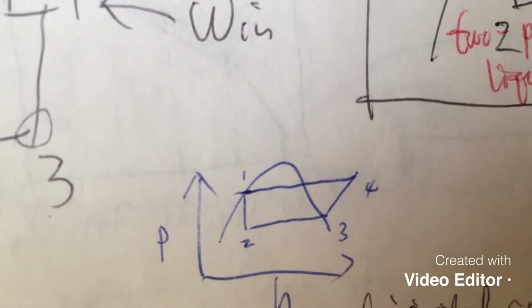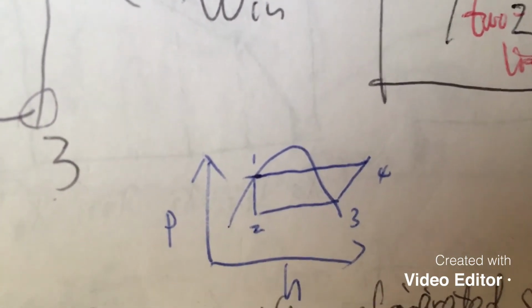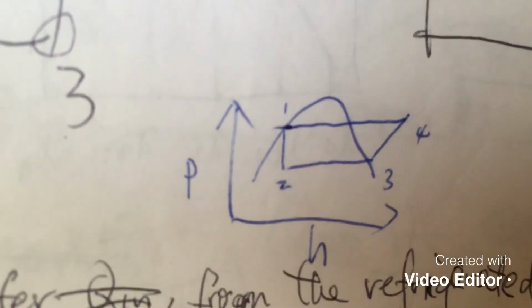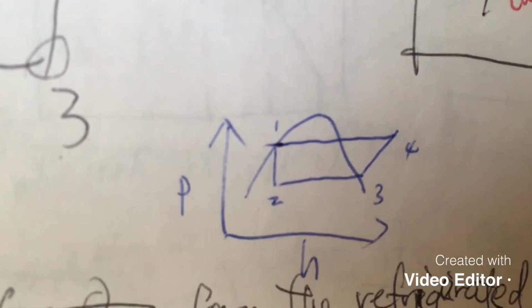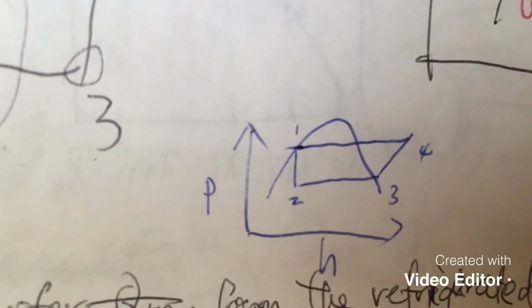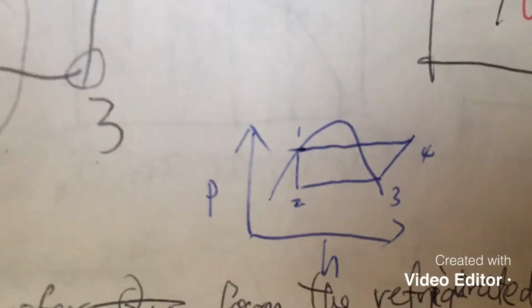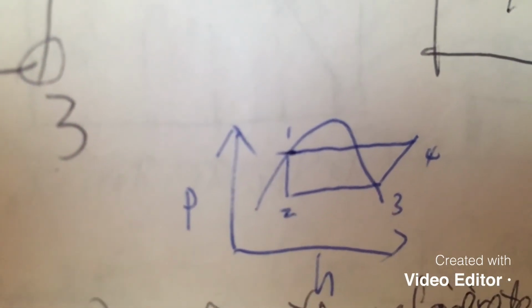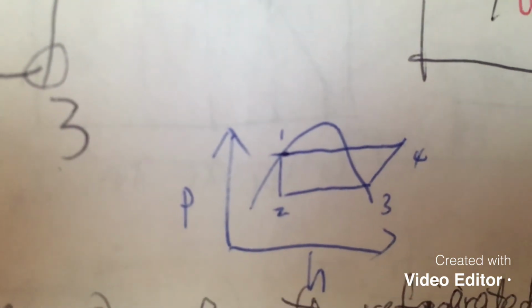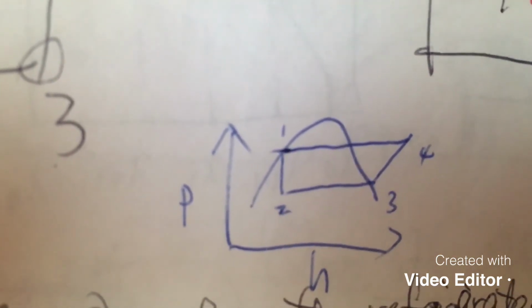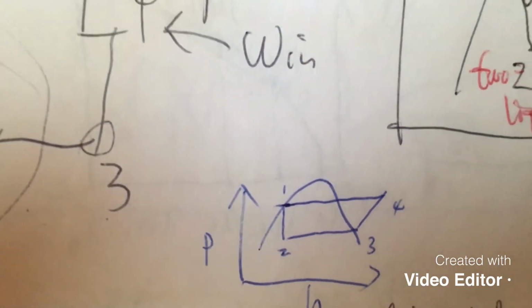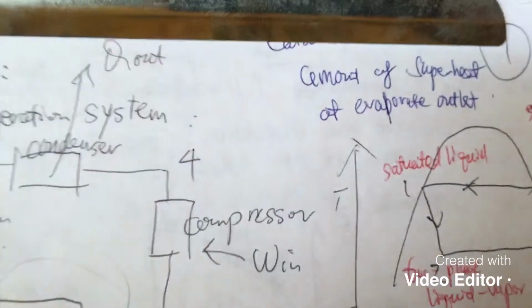And you don't need all the measurement points for enthalpy either, because look at 1 to 2, for example. When you go through the expansion valve, what happens to the enthalpy? Okay, pressure decreases, but enthalpy doesn't change. Okay, straight line down.